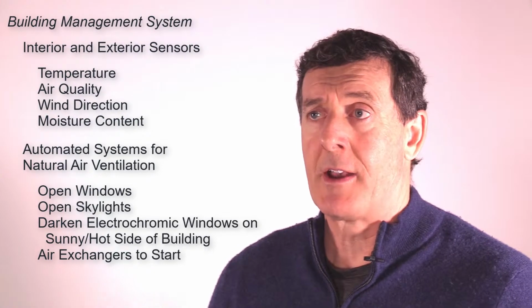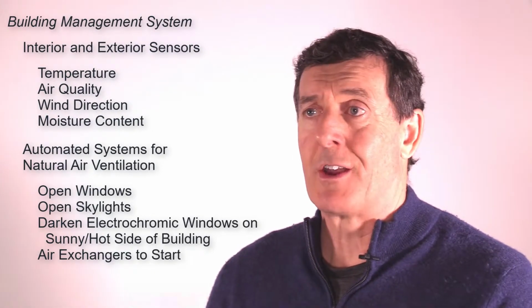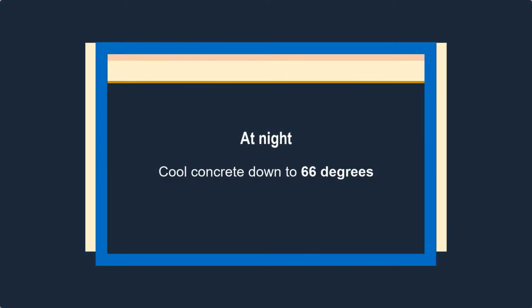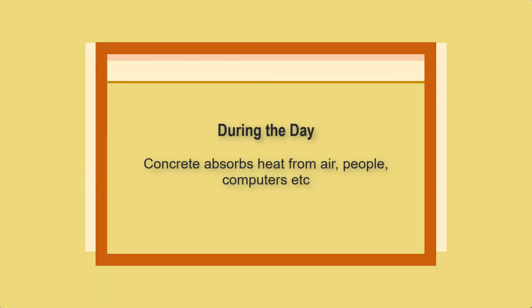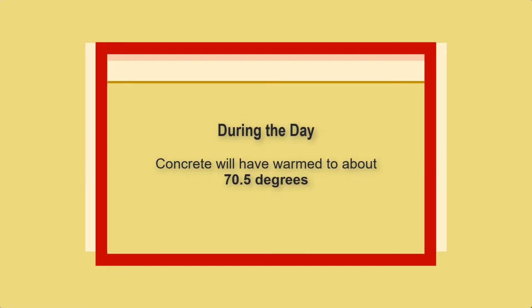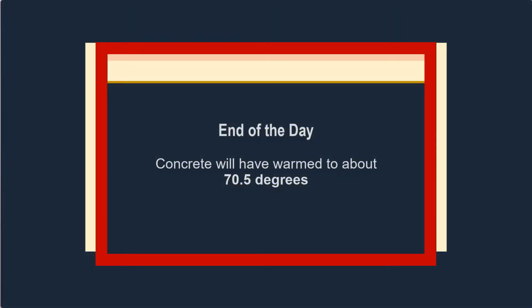If the air quality outside is better than inside, we exchange the air when conditions are appropriate. At night, we'll cool our concrete down to about 66 degrees. During the day it absorbs human heat and computer heat, so the air conditioner never needs to go on—it's a very efficient heat sink. By the end of the day, the concrete will have warmed up to about 70.5 degrees.